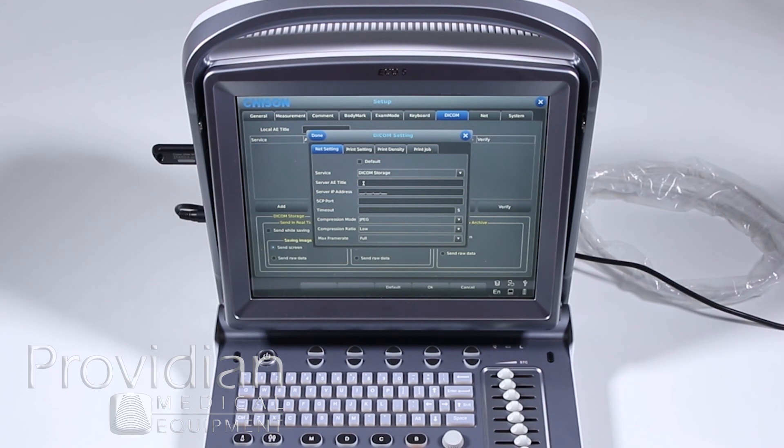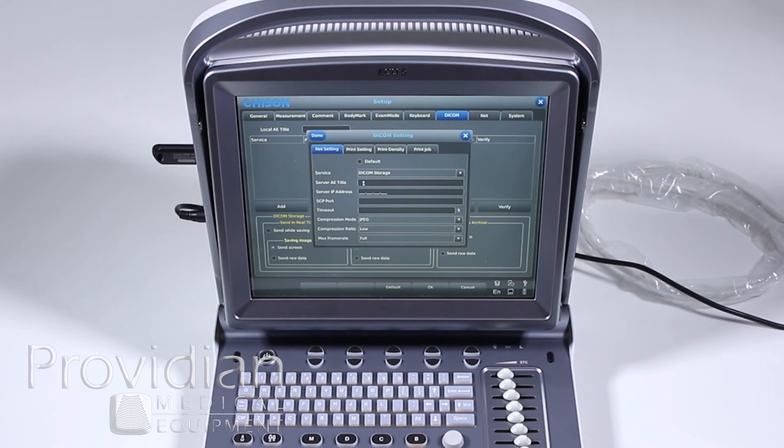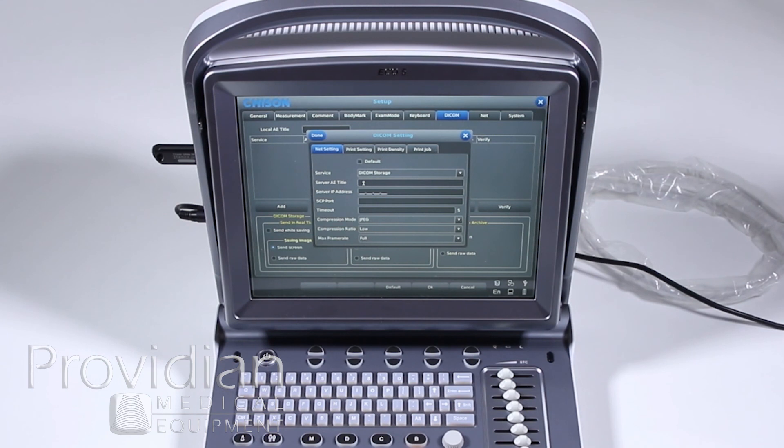They will give you the AE title, the IP address, and the port. And all of these are extremely important and 99% of the problems people have with connecting to DICOM include A, they're not on the network and there's a firewall in between. But the next are the AE title, the IP address, and the port. If those aren't exactly as they were described and how you want to do them, you will not be able to send images. It just simply won't go across.